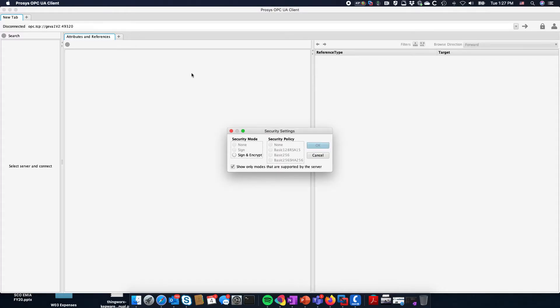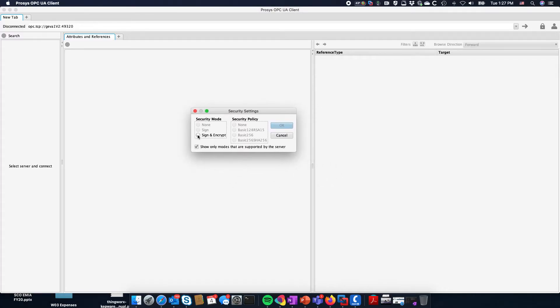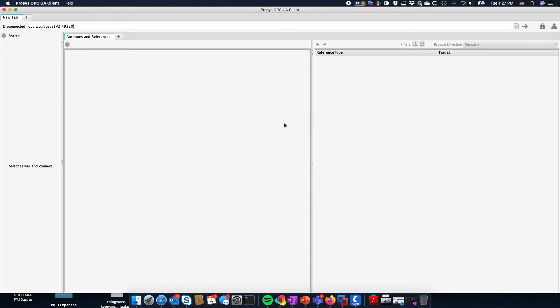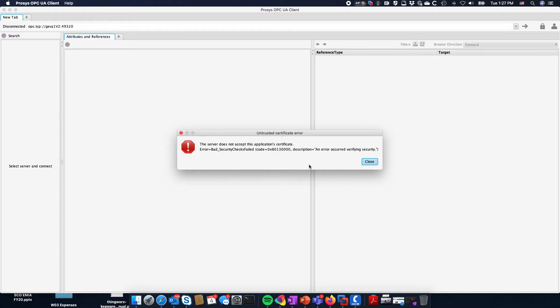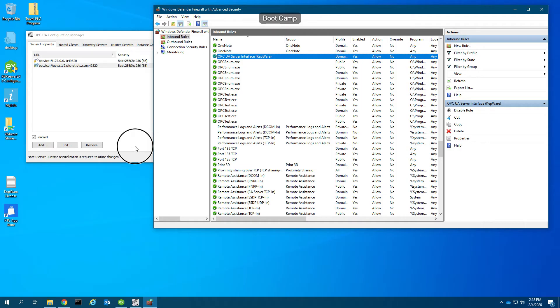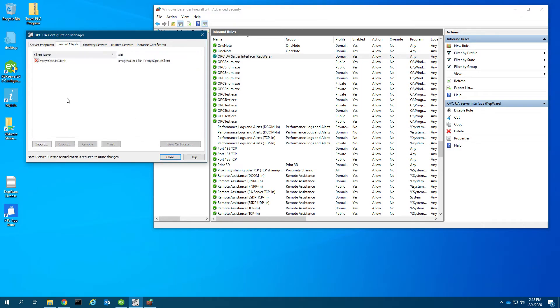We're getting some options back from the server to sign and encrypt, but it says the server does not accept this application certificate. We received a certificate from Kepware and now we're exchanging a certificate back which was refused by Kepware.